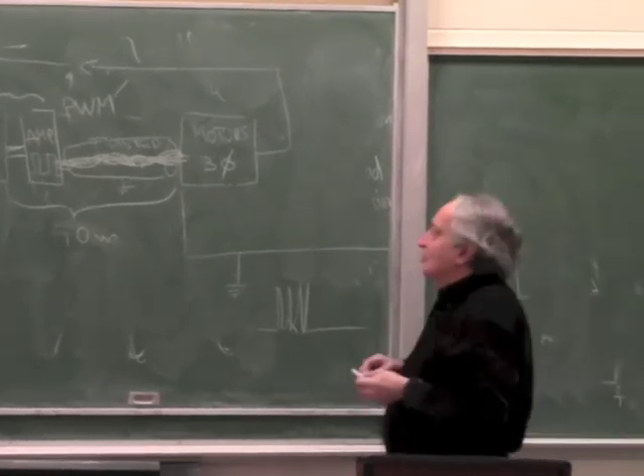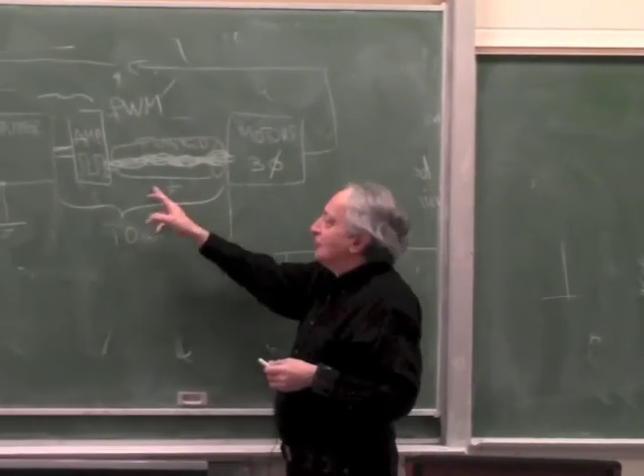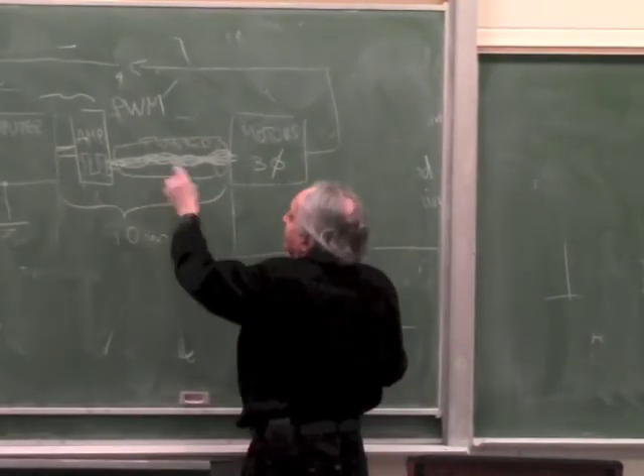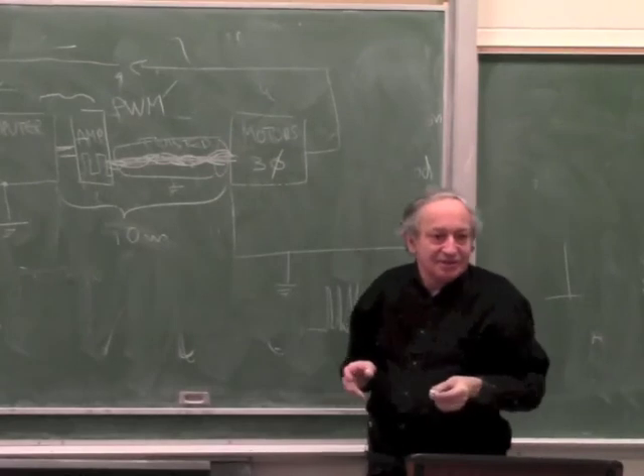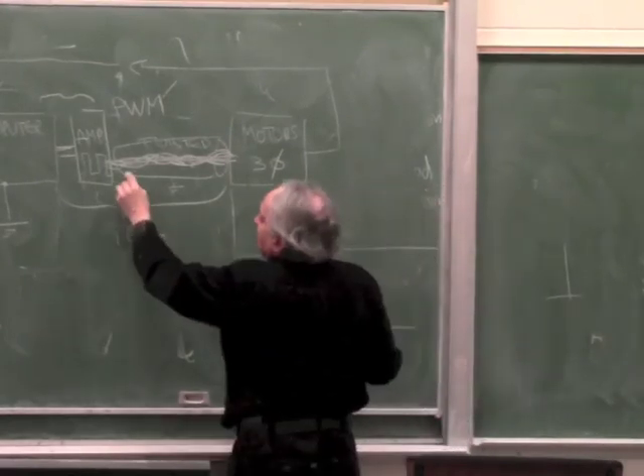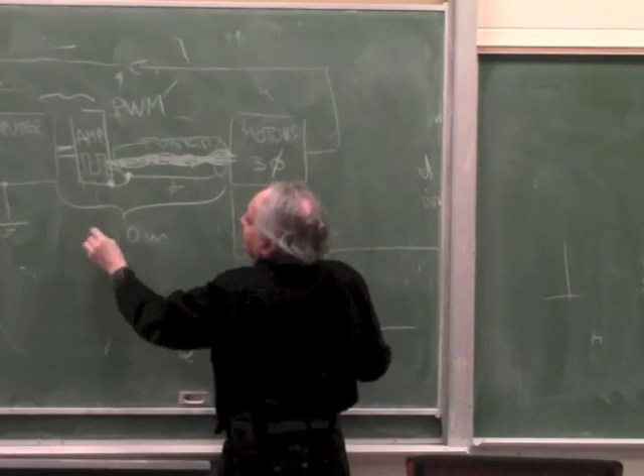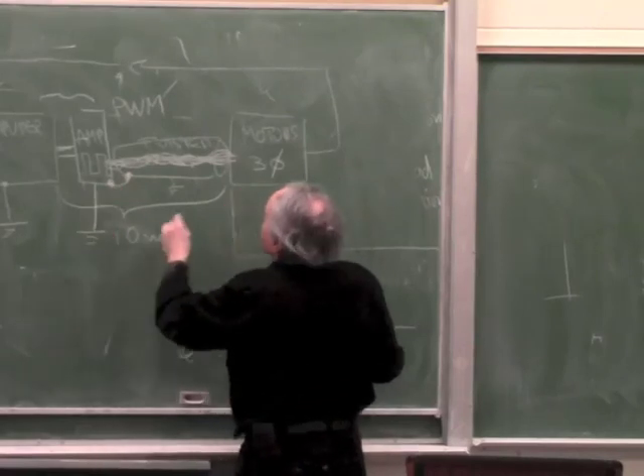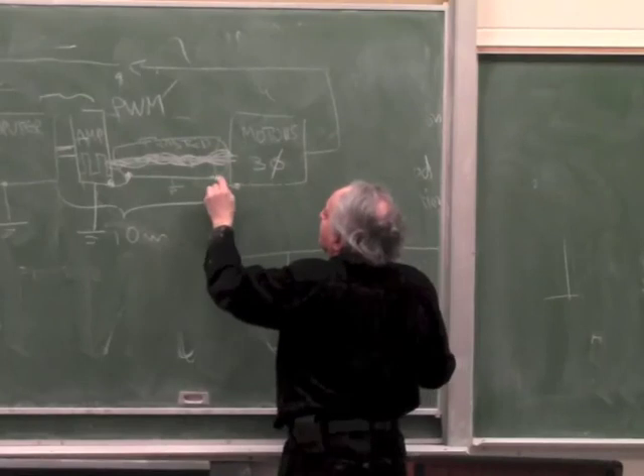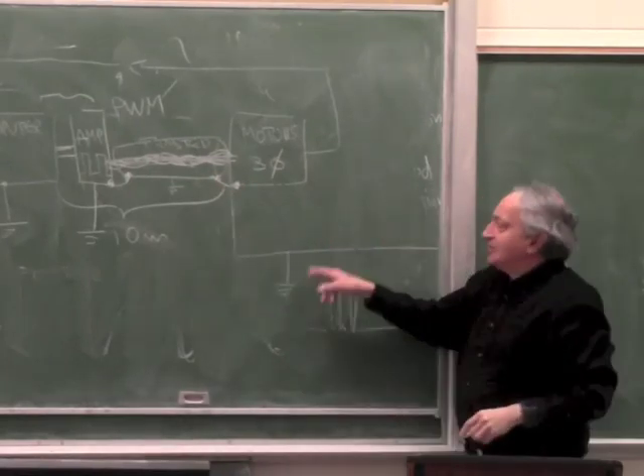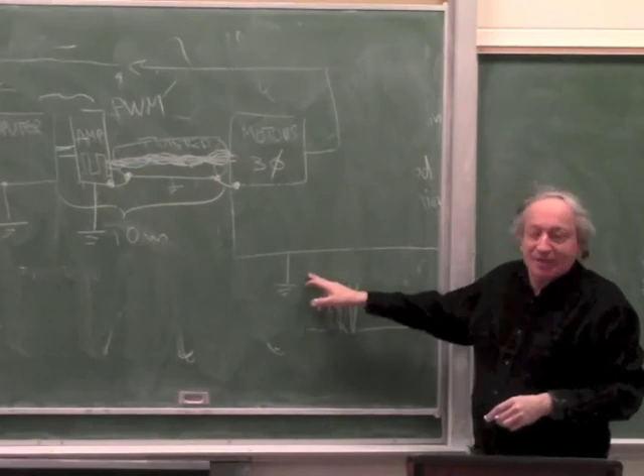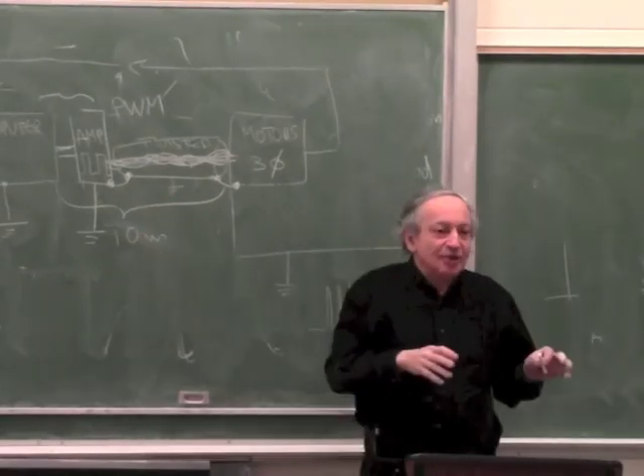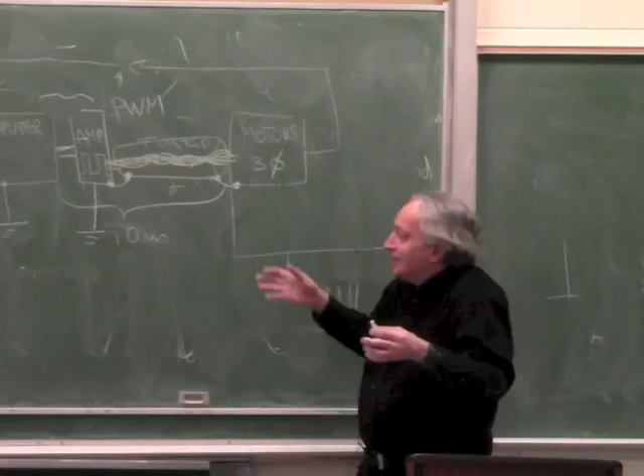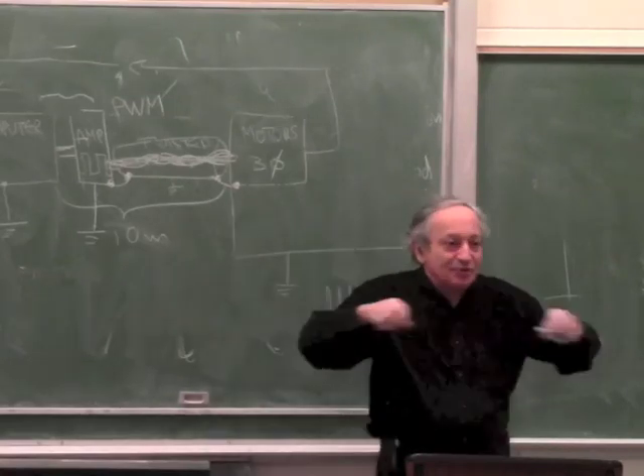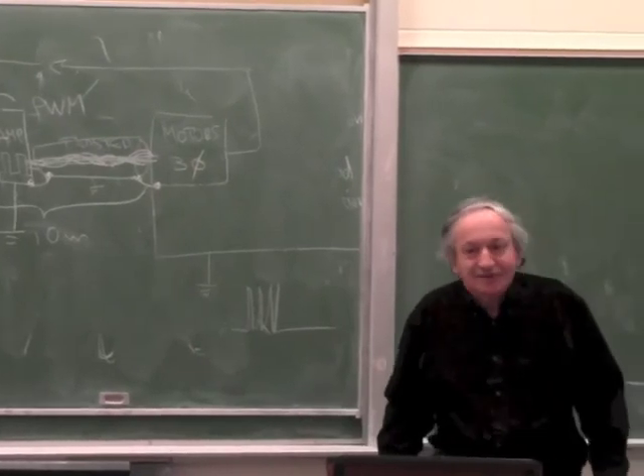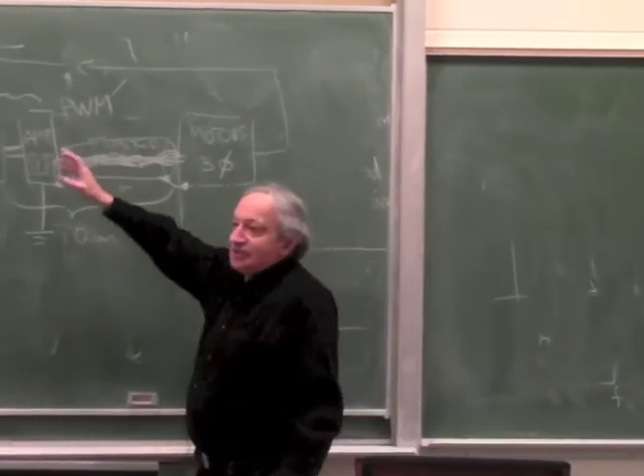So you still have to shield it, but since this isn't a coax, you can ground the shield at one end or both — it doesn't matter. Typically you'll ground it at both ends: connect the shield to the amplifier, which is grounded, and to the motor, and the whole metal structure will be grounded by code. But it's not grounded at both ends to make it behave like a coax — it's grounded at both ends just because of how codes usually work, like a conduit that must be grounded at both ends. The important thing here is that it's shielded, not that it's coaxial.